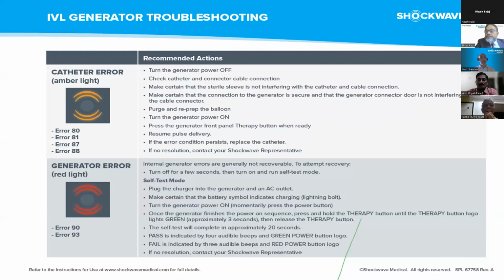and it may reset what the error code was. But from my short-term experience, and what I'm learning from my colleagues within the US and Europe, the majority of these are connector issues or air within the catheter. Primarily, I'm being told it is air in the catheter. So priority number one is turn off the generator, turn it back on, check your connections, and then purge and re-prep the balloon. After that, from what I have seen in my experience, this resolves the majority of those error codes. If it does not, it is always down to the connector or the connector cable, starting with replacing the catheter to get rid of the code, if not looking at having a spare connector cable in the cath lab to replace that.